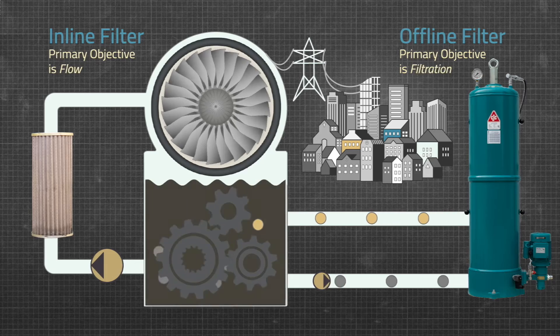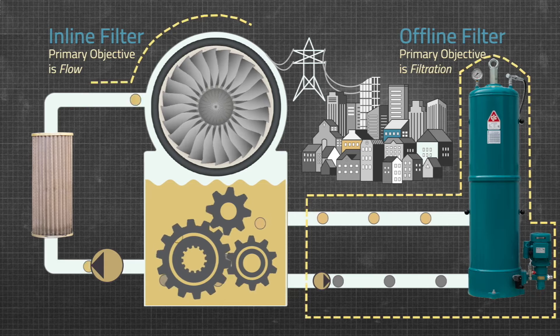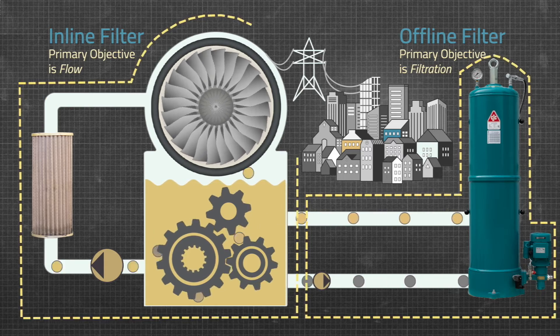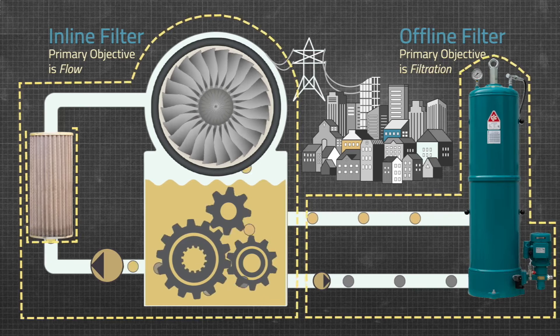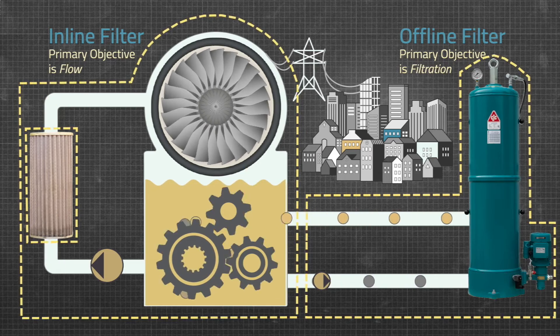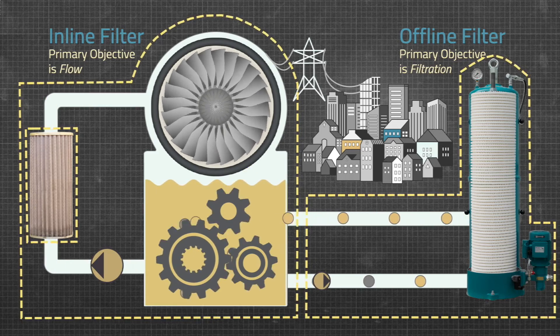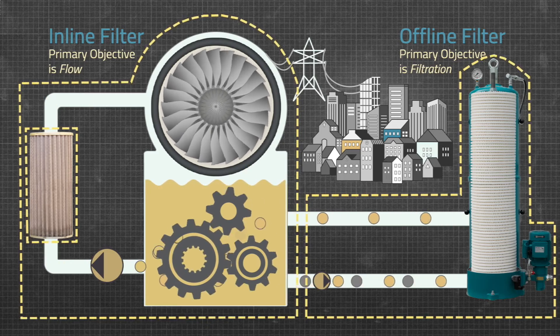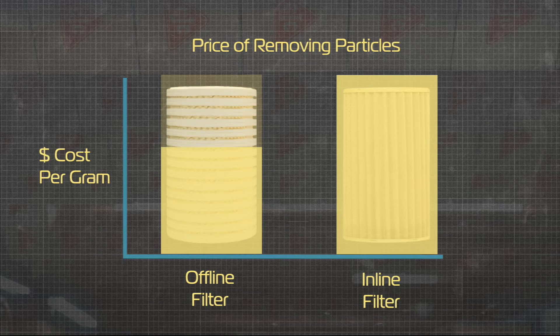There are a number of features and benefits inherent to an offline filtration system. Offline filters can be installed and maintained without disruption to the main system. Offline filters do not affect main system flow or pressure. Offline filters improve the lifespan of inline filters. Offline filters can use far denser media, resulting in finer filtration and higher holding capacity. Ultimately, offline filters can remove contaminants at a cost per gram in the neighborhood of one-tenth that of inline filters.